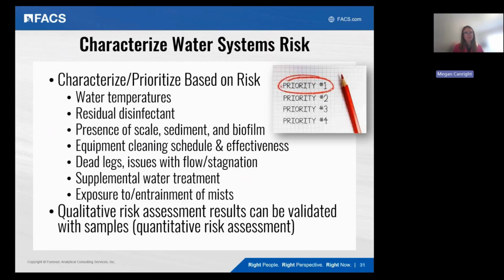Are water temperatures in the growth range of the organisms? Is there sufficient residual disinfectant? Is there presence of scale, sediment, or biofilm? Compiling all that information helps you collate all the areas of risk and prioritize them, so you're addressing the highest risk areas first when making recommendations for control measures.